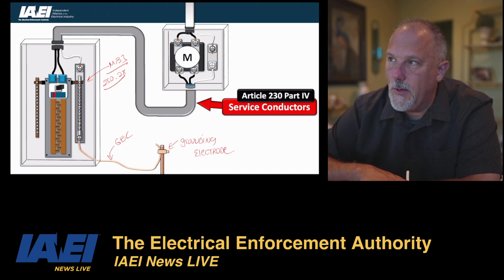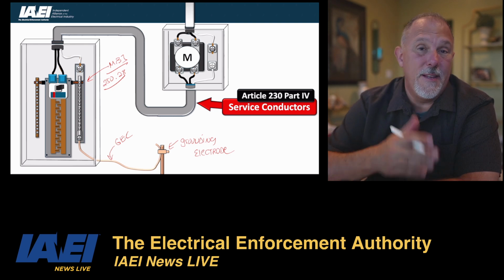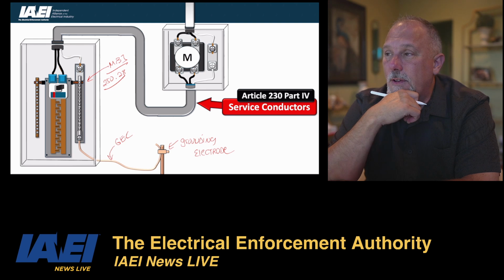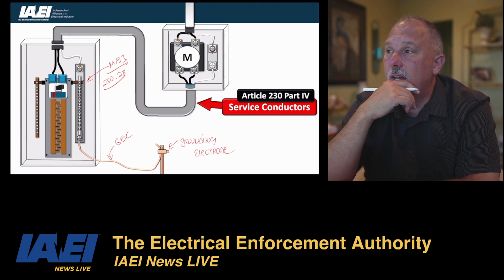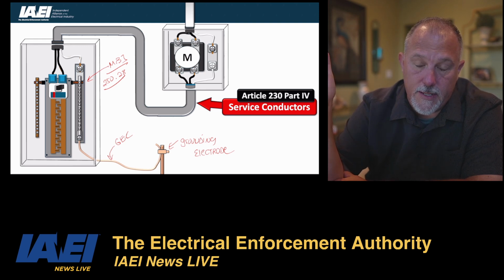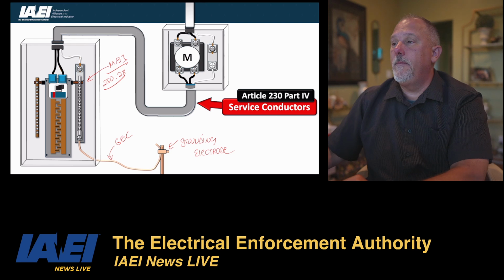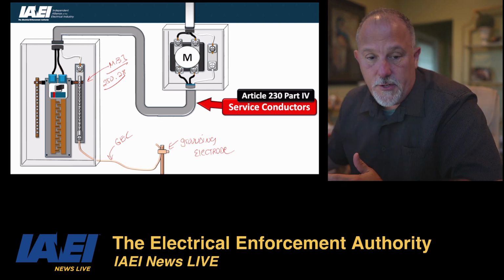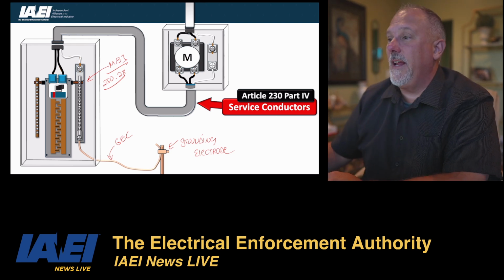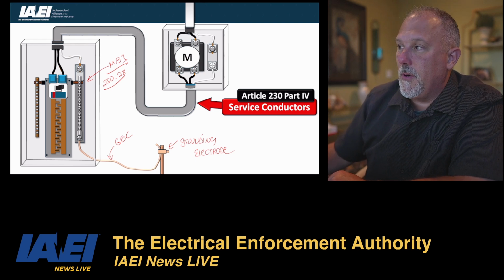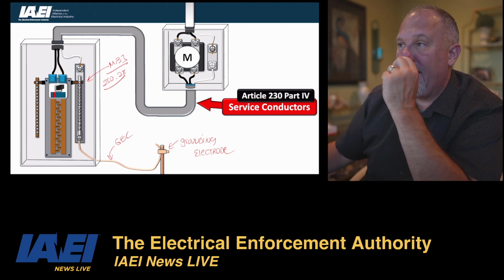So I don't know that you would have to be thinking about the main bonding jumper in sizing for that equipment. Maybe you know where those details will come into play. You shouldn't be field fabricating anything like this out in the field. If the manufacturer forgot to include it, then call the manufacturer and have them send you the appropriate part for that application.